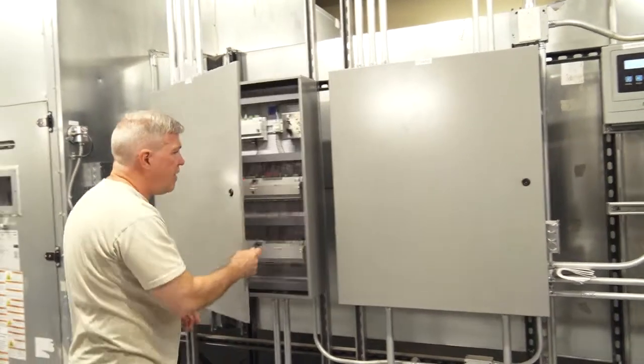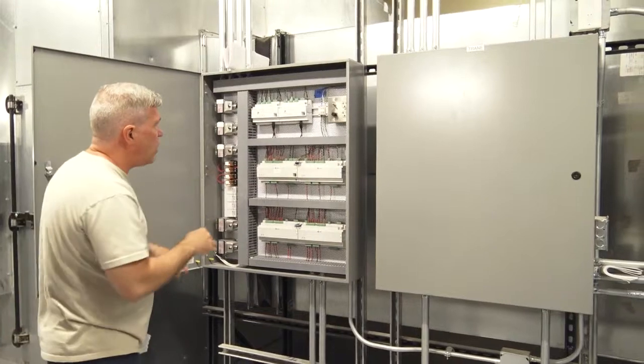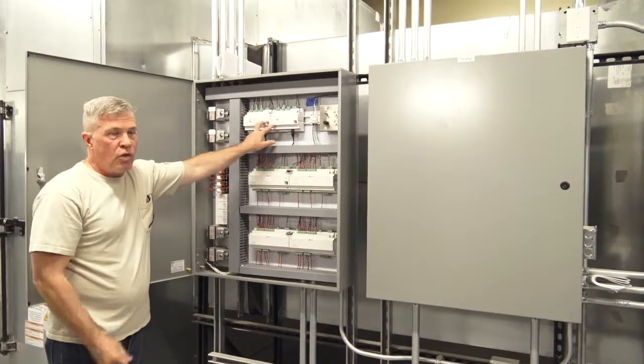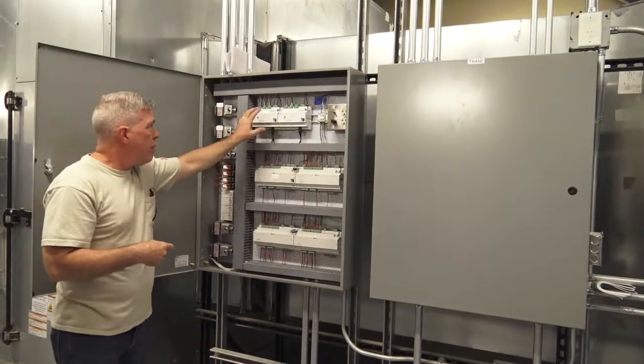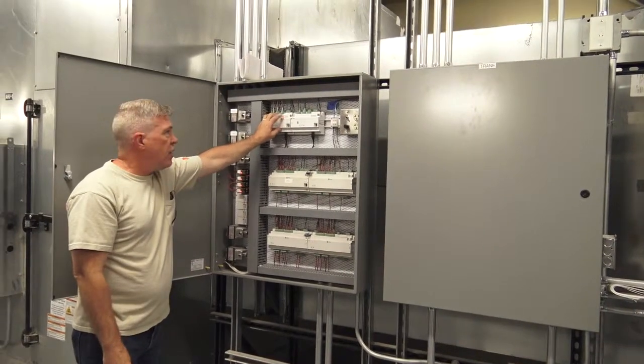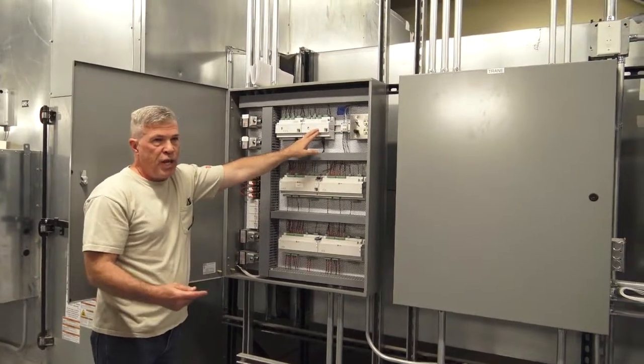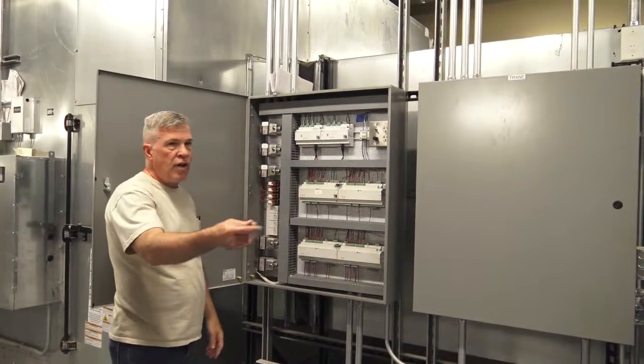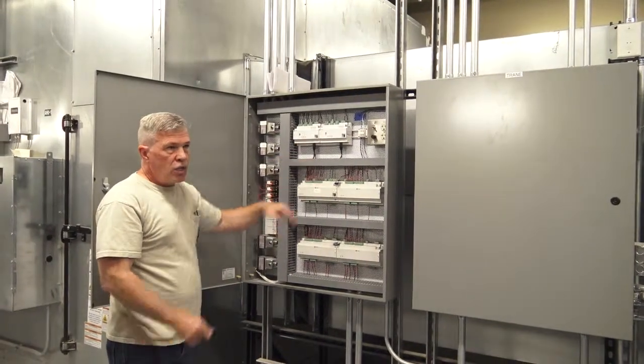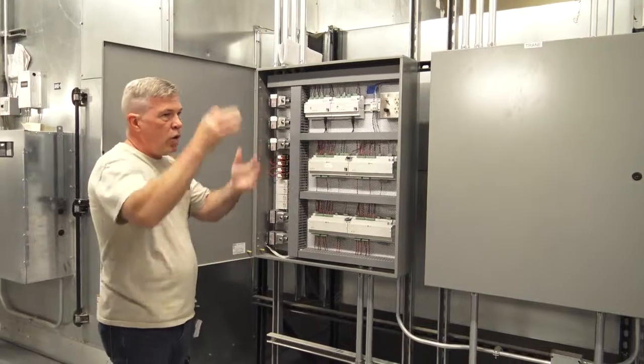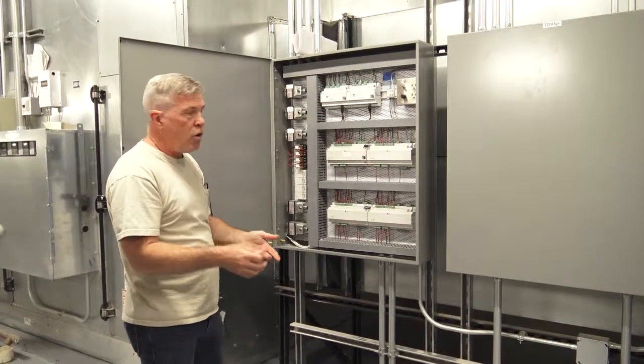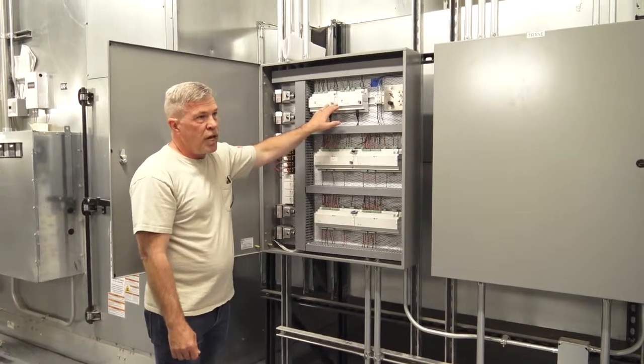This first one is kind of your main panel as far as your two front end controllers, there's two SCs here. This one is kind of the brains of the building. This one's basically just a bridge for any extra devices that wouldn't fit on here. So if for some reason you're having a problem with a whole section of the building communication down, this is a place to go and check first.